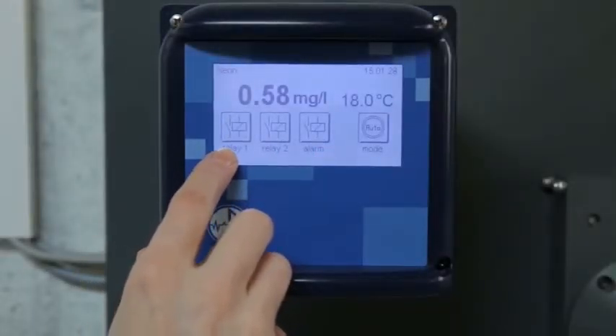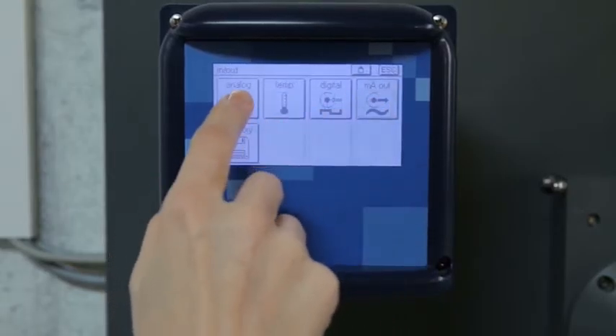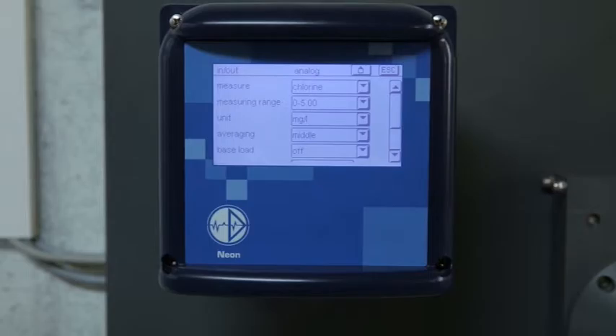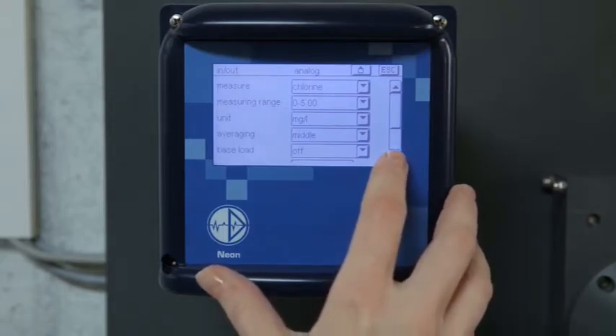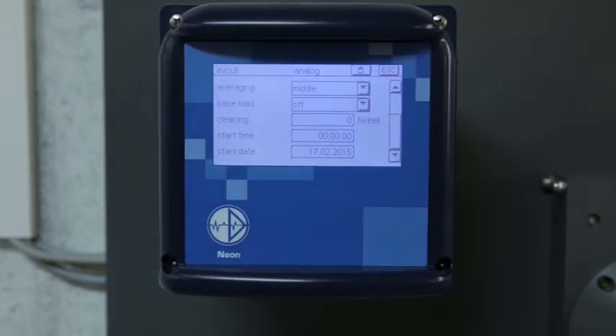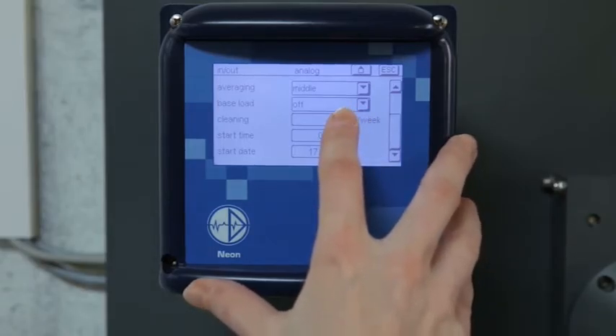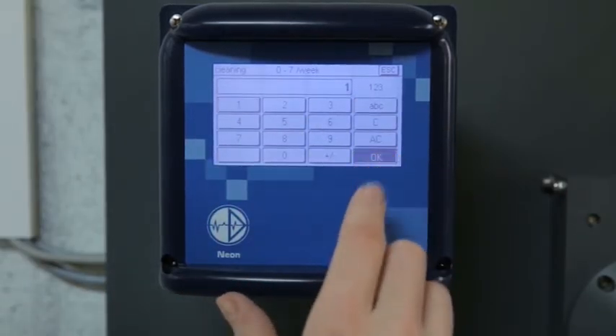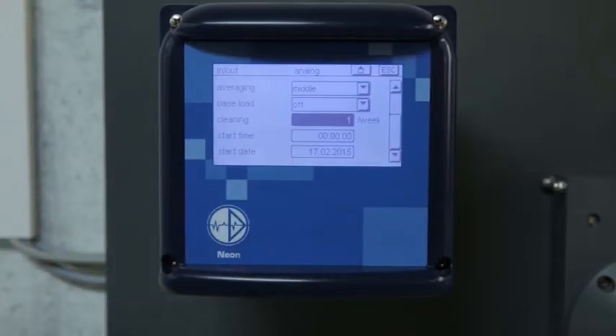Krypton systems are equipped with our patented automatic sensor cleaning, which cleans the sensor electrodes in regular intervals. Before activating the cleaning function, make sure you set the correct time and date. Check time and date to make sure the starting date is not in the past. Then select the cleaning intervals. You can choose between 0 and 7 times per week. For most applications, 1 cleaning cycle per week has proven absolutely sufficient. We recommend carrying out cleaning during night hours or at times when relatively low fluctuation can be expected. During the cleaning procedure, the milliampere outputs are frozen.